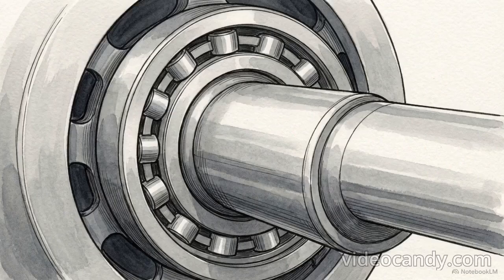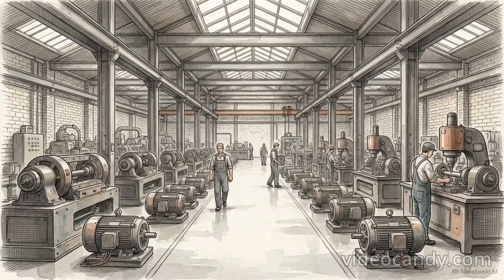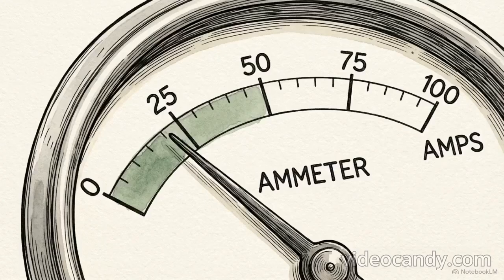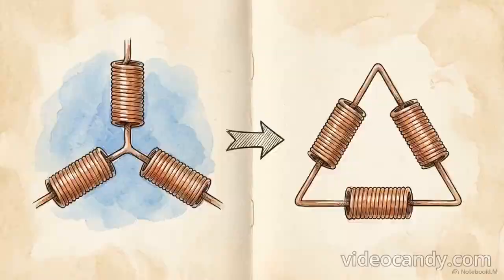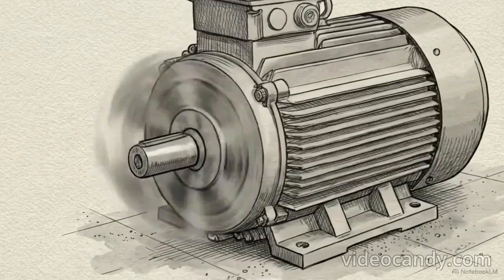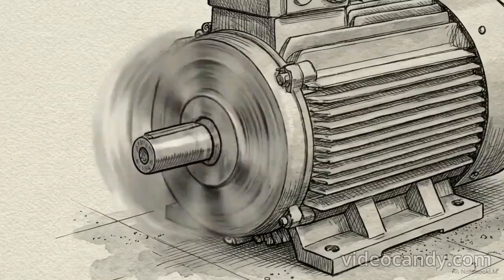While the motor has less physical pushing power, this 1/3 reduction drastically limits the thermal degradation of the insulation and reduces the mechanical shearing forces on the rotor shaft. The star configuration protects the motor's operational lifespan. By artificially bottlenecking the available voltage, it forces a throttled, manageable current draw during the system's most vulnerable moments of operation.